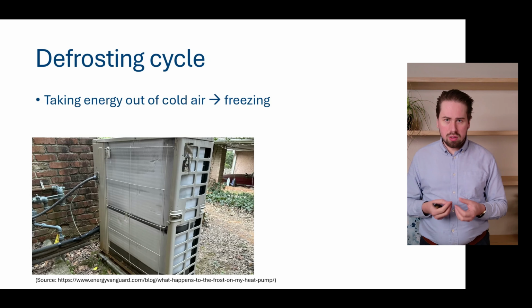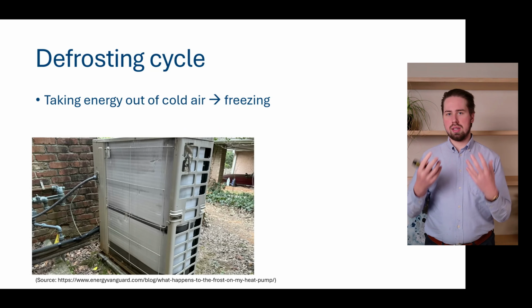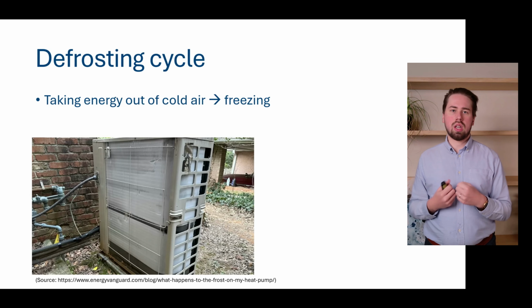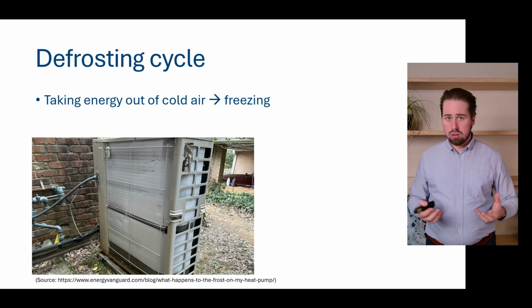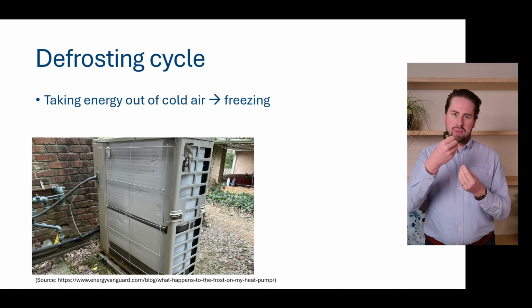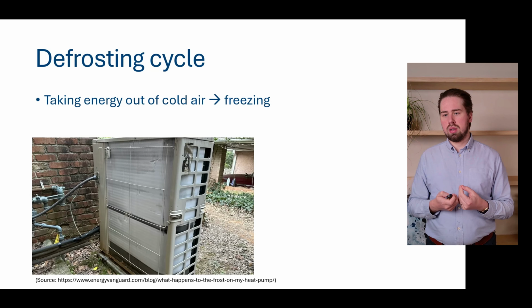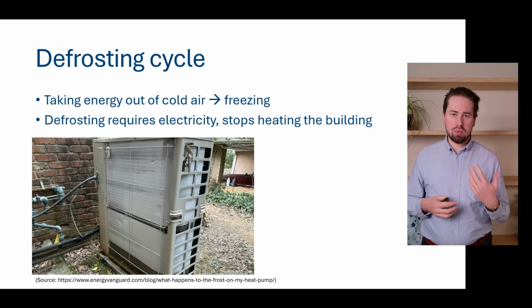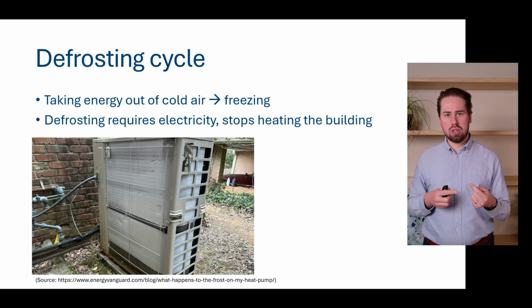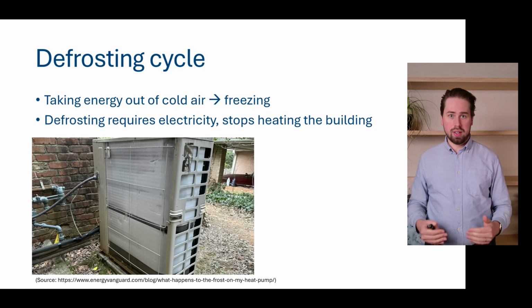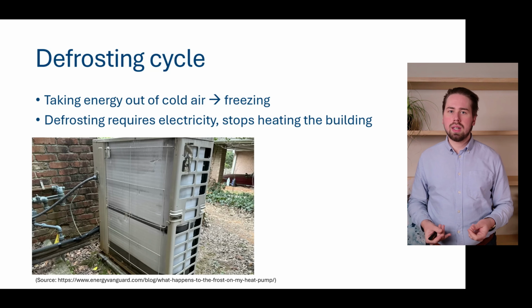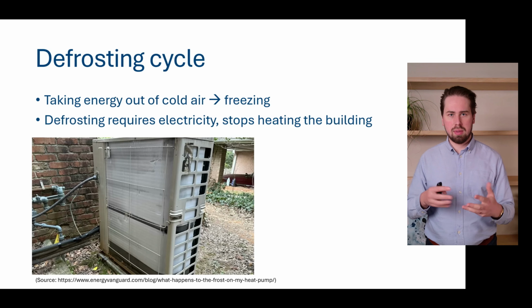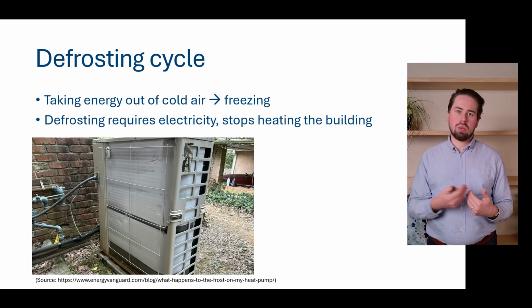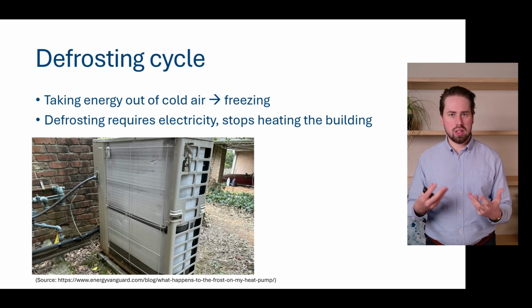Now, another issue with air source heat pumps is the defrosting cycle. When an air source heat pump is heating your building, it's taking the energy out of the air. And when it's cold outside, or it's 2 degrees Celsius, for example, it cools down the air and the moisture freezes to the heat exchanger in the air source heat pump. So from time to time, the heat pump has to reverse its operation, actually heating the heat exchanger to melt the ice away in order to keep functioning. Because when everything is frozen, there is no way for new air to pass through and to exchange heat.